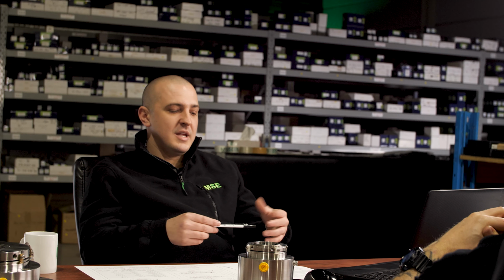Do you know what the root cause was for that problem? Yeah, they're running a Plan 52, API Plan 52 setup. That's a tandem seal with an external barrier chamber or reservoir. For this plan to work, it's critical that there is flow going between the mechanical seal and back to the reservoir. Otherwise you get a positive feedback loop where the friction of the seal faces causes heat, which causes more friction, and without that flow there's nowhere to dissipate that heat. So it just kept getting worse until the seal faces would either wear extremely or explode.